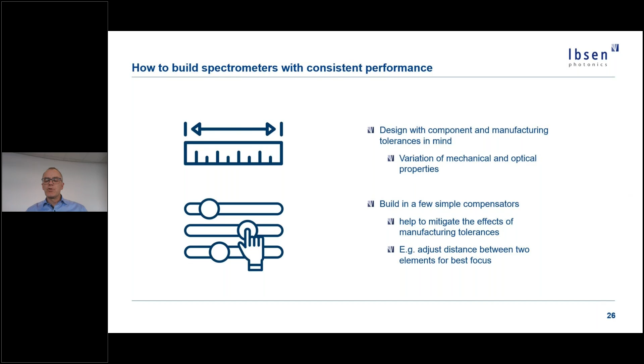If the spectrometer design is done well, the performance of the spectrometer will stay within reasonable limits, but if the design is done badly, the performance can vary a lot from unit to unit. In case of tolerances that are hard to compensate in the design directly, it can be a solution to build in a few compensators. This could be a simple mechanical adjustment of the distance between, say, the detector and the last lens in order to compensate for variation in focal length and thereby adjust for best focus and optimum resolution.